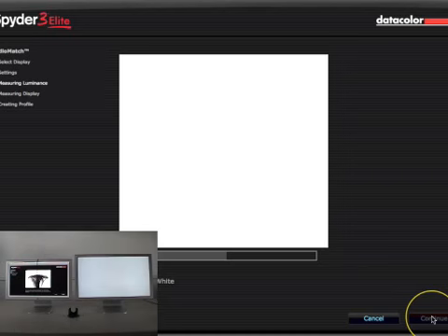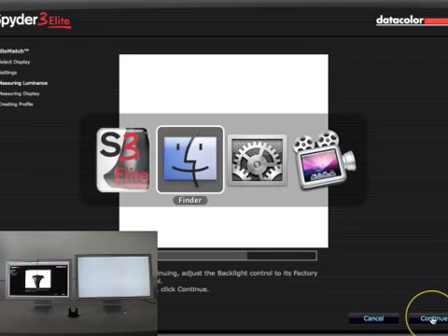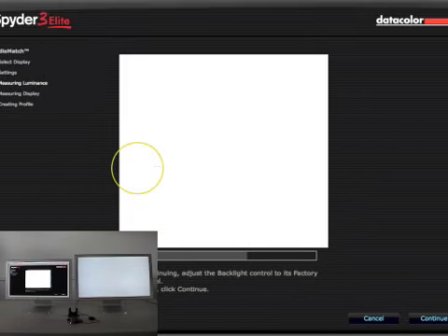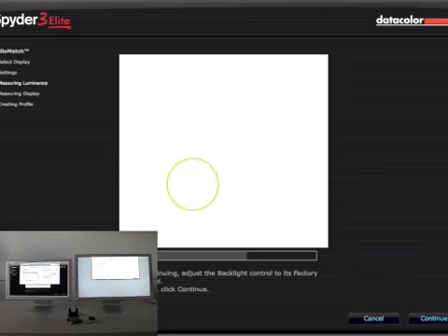The maximum white luminance of the monitor is measured. The final screen asks you to return the luminance control back to its default position. Remove the sensor from the display and adjust the monitor controls. These steps will be repeated for each monitor that is being calibrated in the StudioMatch process.